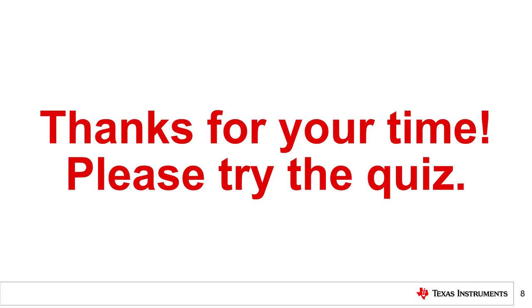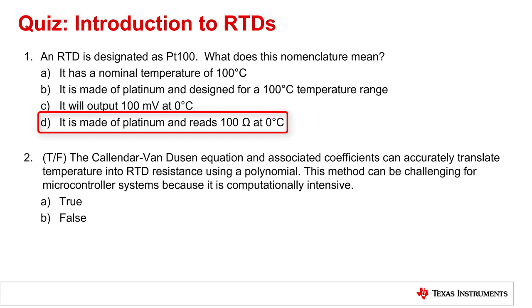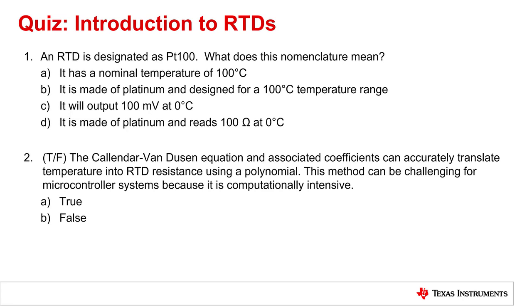That concludes this video. Thank you for watching. Please try the quiz to check your understanding of this video's content. Question 1: An RTD is designated as PT100. What does this nomenclature mean? The correct answer is D — it is made of platinum and reads 100 ohms at 0 degrees C. Question 2: True or false — the Callendar-Van Dusen equation and associated coefficients can accurately translate temperature into RTD resistance using a polynomial. This method can be challenging for microcontroller systems because it is computationally intensive. The correct answer is A, true.